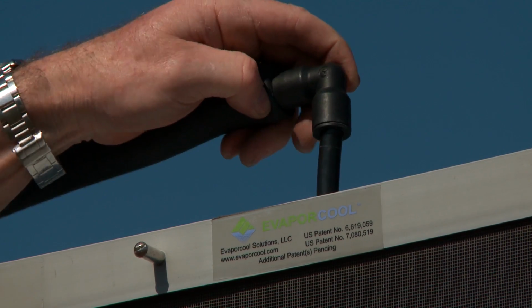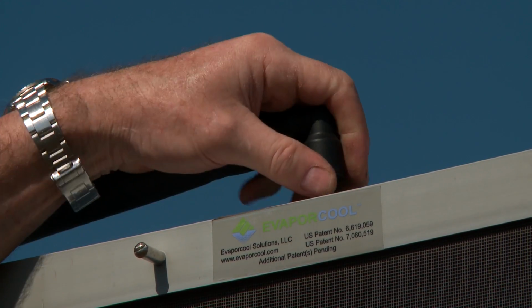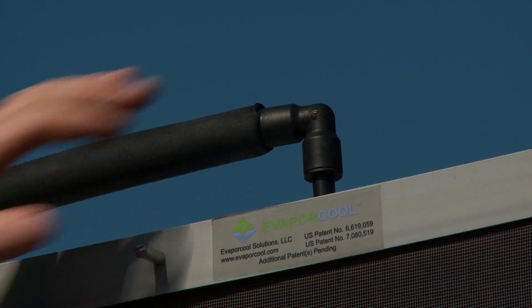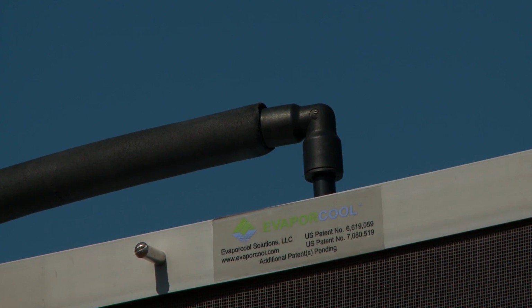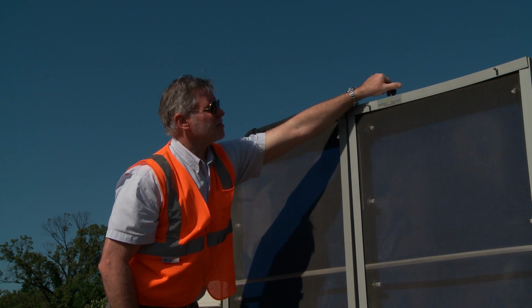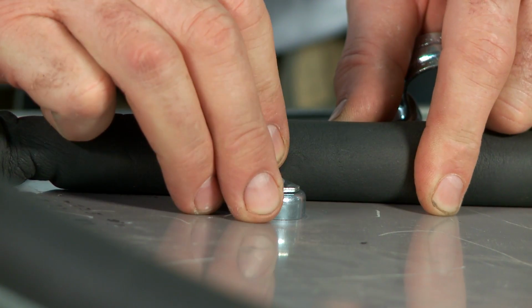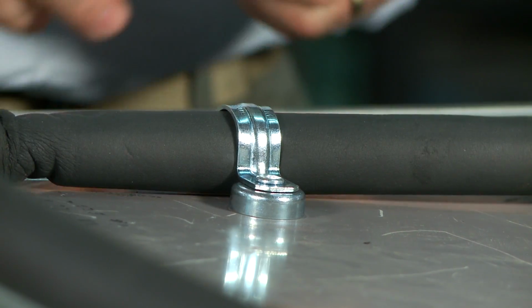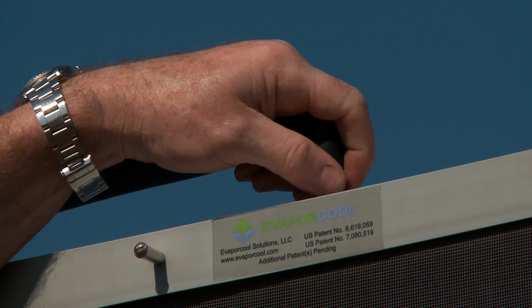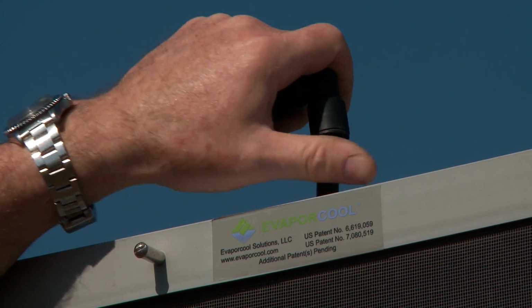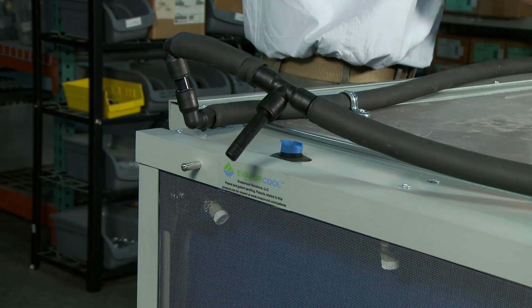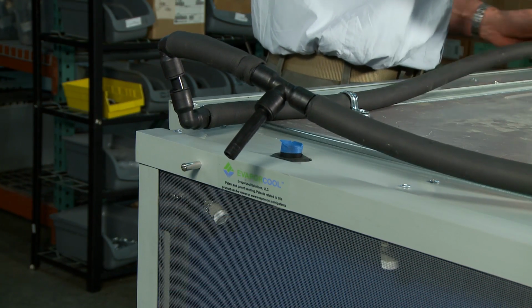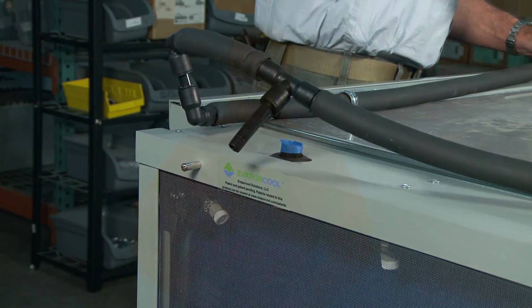Evaporcool provides the tubing, and making the connections does not require any tooling. Simply ensure a square cut and firmly press the tubing into the fitting. Tug to ensure a tight connection and use caution not to have too tight of a bending radius along any segment of tubing. Secure tubing to the unit with the included magnetic tubing straps. To release the piping, press the collar in on the fitting and pull the piping. Note that you need to leave the last connection open along with the tape on the frame tubing connection in place in preparation for system startup.